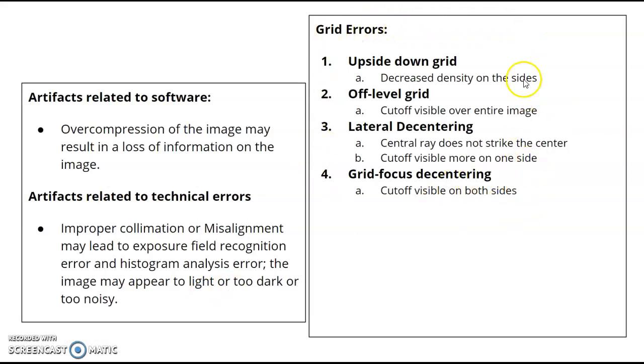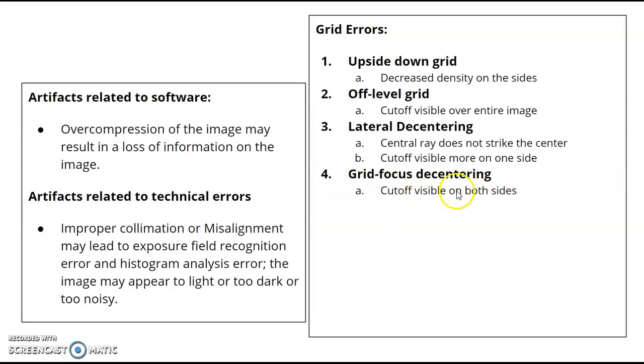Here are four grid errors to know. The upside-down grid results in decreased density on the sides. An off-level grid can happen in ER situations where the cassette under the patient is off-level — you'll have cutoff visible over the entire image. Lateral decentering is when the central ray is not striking the center of the grid, and cutoff is more visible on one side. Grid-focused decentering occurs when you're outside the focused distance range — if you're past 72 inches, you'll get cutoff visible on both sides.